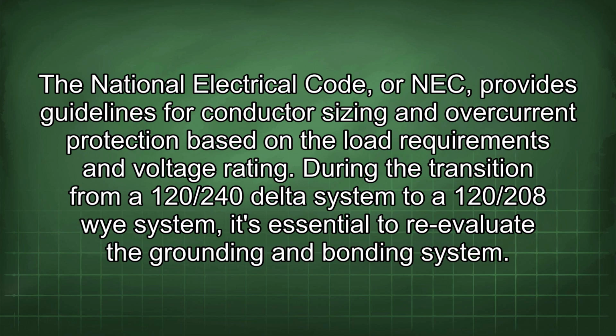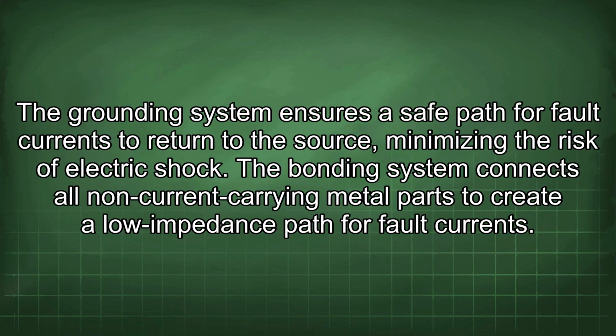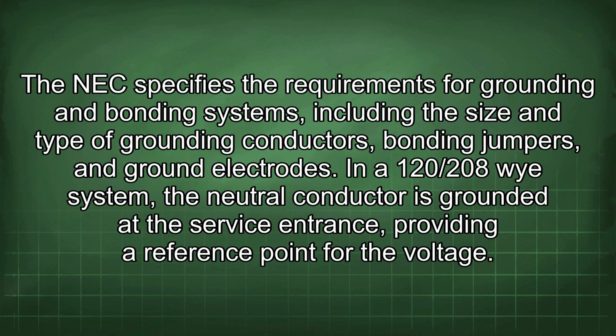During the transition from a 120/240 delta system to a 120/208Y system, it's essential to re-evaluate the grounding and bonding system. The grounding system ensures a safe path for fault currents to return to the source, minimizing the risk of electric shock. The bonding system connects all non-current carrying metal parts to create a low impedance path for fault currents. The NEC specifies the requirements for grounding and bonding systems, including the size and type of grounding conductors, bonding jumpers, and ground electrodes.